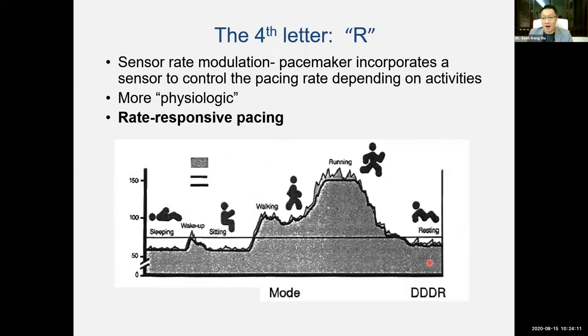The fourth alphabet or fourth letter here, the R, whether with the R or without an R, I shall not be able to point too much because there are a lot of different technologies proprietary to different brands. But suffice to say that if you have R, the pacemaker is a smart one, smart in the sense that it can afford a more physiologic pacing experience for the patient, because the R means rate responsive pacing.